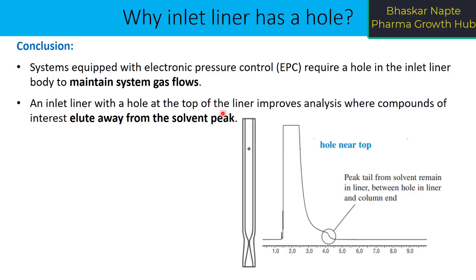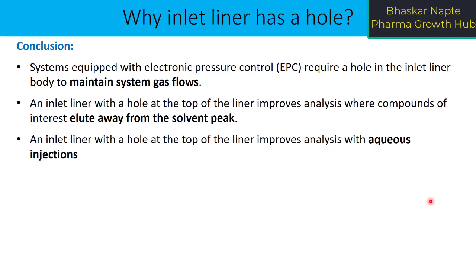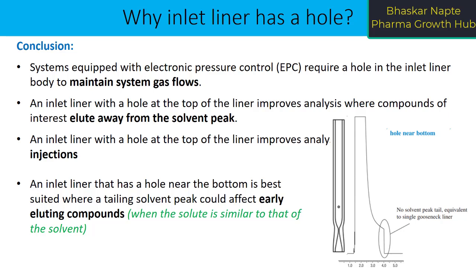An inlet liner with a hole at the top improves analysis where compounds of interest elute away from the solvent peak — the peak tail from the solvent remains in the liner between the hole and the column end. You can see a chromatogram for your understanding. This liner with the top hole is also preferable for samples containing aqueous diluent. An inlet liner with a hole near the bottom is best suited where a tailing solvent peak could affect early eluting compounds, or when the solute is similar to that of your solvent. If there is poor resolution between your solvent and analyte because of high solvent tailing, you can use a liner with a hole at the bottom and get improved resolution.